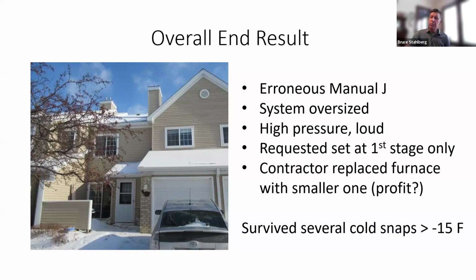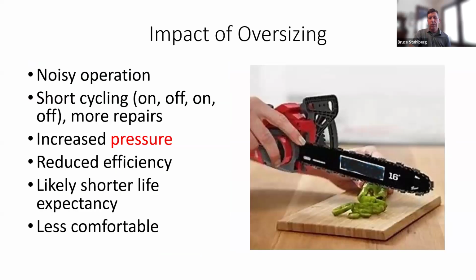By the way, we had 15 below. And I called the customer and she's like, yeah, it's just fine. So it passed a real world test, and that's the best way to really test. So oversizing is a problem. They can be very noisy. Short cycling, it'll come on, satisfy the thermostat, turn off. You get more repairs, increased pressure in the system, reduced efficiency, shorter life cycle. When something comes on and off a lot, there's going to be more repairs and shorter life cycle, and less comfort. So there's a number of really good reasons why we want to get the sizing more accurate.